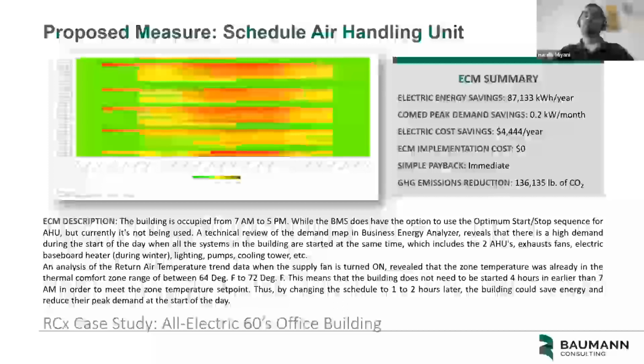So we did all the investigation calculations from our end, and based on the return air temperature, we were able to see that even if this building starts the system at 6 a.m., they will be able to reach the desired set point within 25 to 30 minutes. This is a strategy that we use, looking into the graphs to determine the ECM and doing all the engineering calculations based on that.